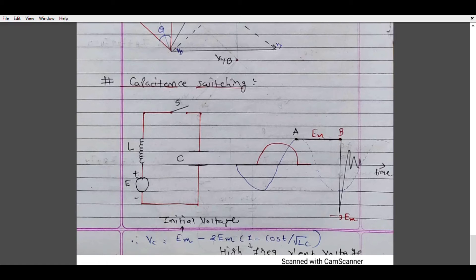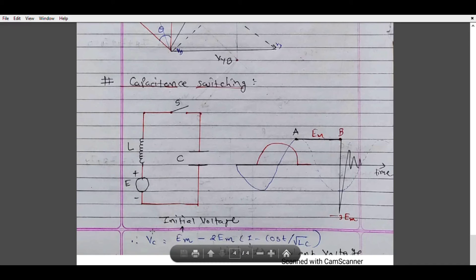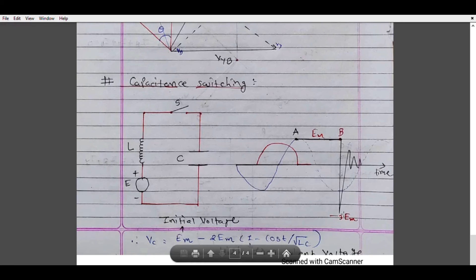As the capacitor is isolated from the source it retains its charge. Now at instant b — half a cycle later — the voltage across the switch reaches a peak value of 2Em, and this voltage reignites the arc, causing an oscillatory transient. The voltage across the capacitor is given by: Vc = Em - 2Em(1 - cos(t / √LC)). This can increase the maximum value of the voltage to minus 3Em, as shown in the figure. The peak value is 3Em in the negative direction.